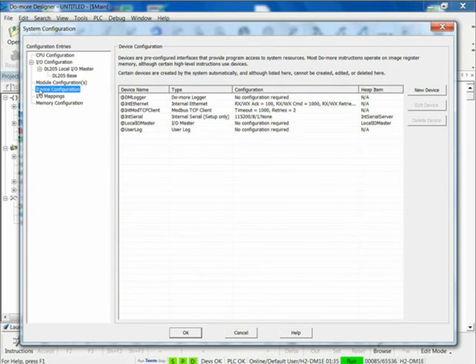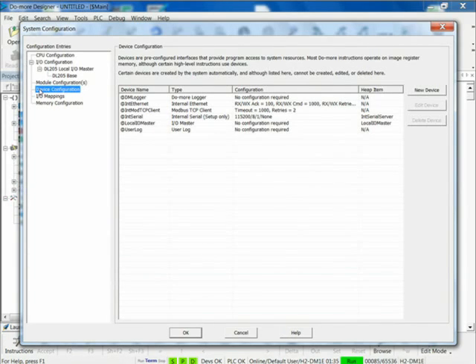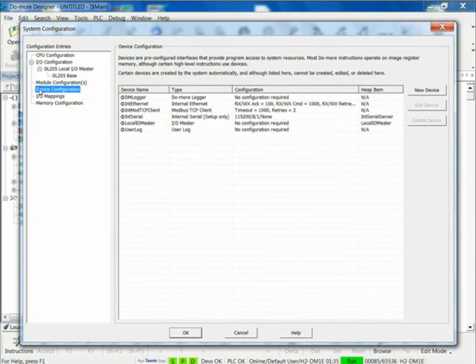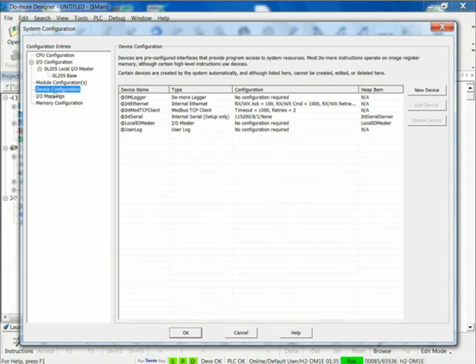I have a serial port, but what protocol am I running on that port? It might be a Modbus Master, it might be Modbus Slave, it might be a program control where I'm doing ad hoc, I'm writing ladder logic for it. So you'd have to do that configuration here. So basically also under Devices, I take it if I want to put an email server in so it could send emails, I would load a device driver for the email.